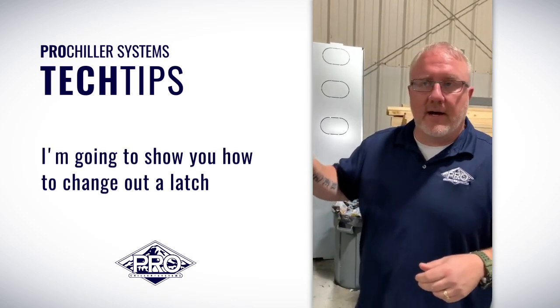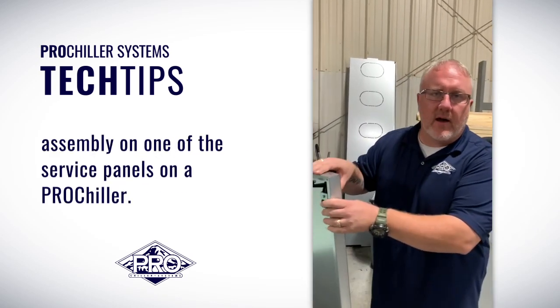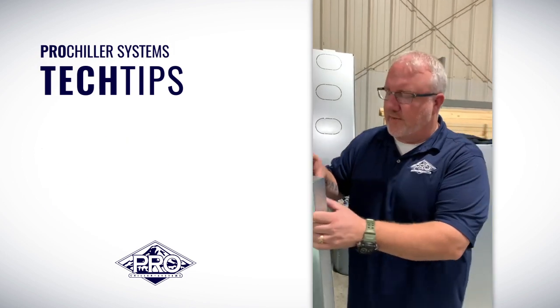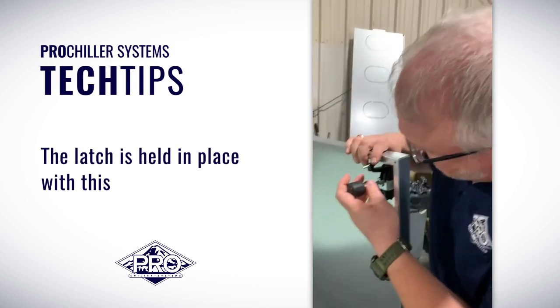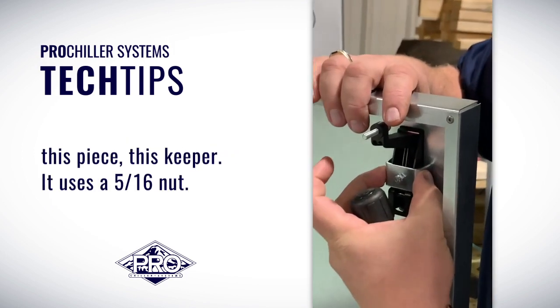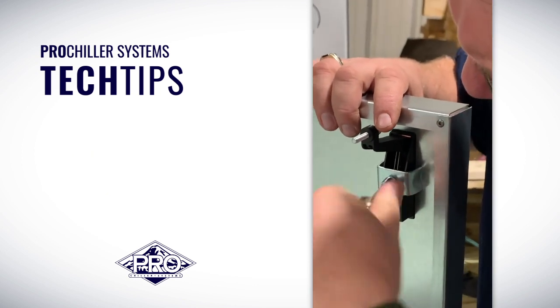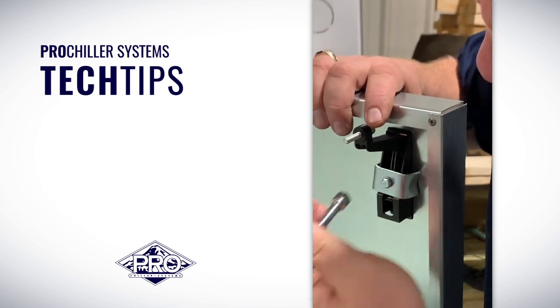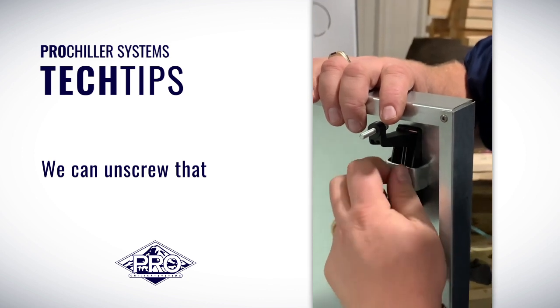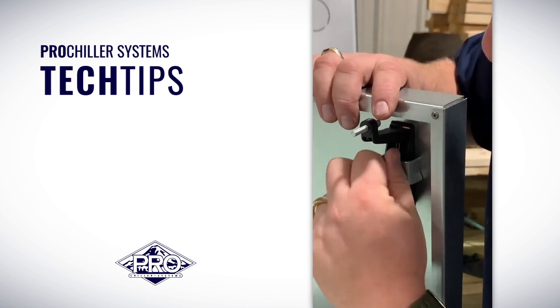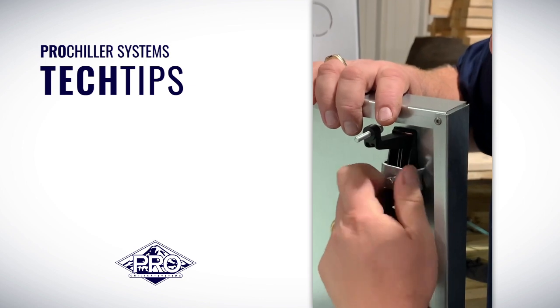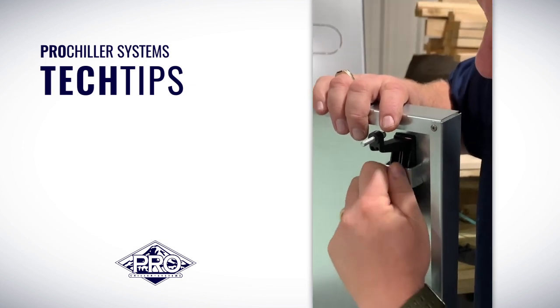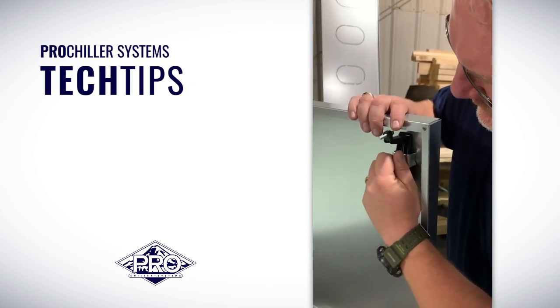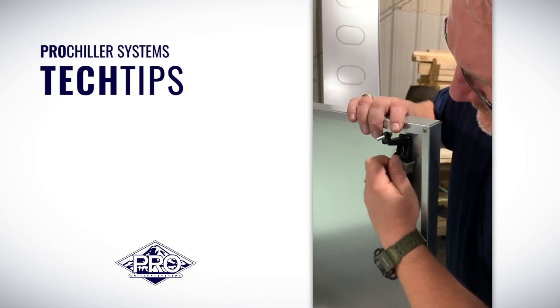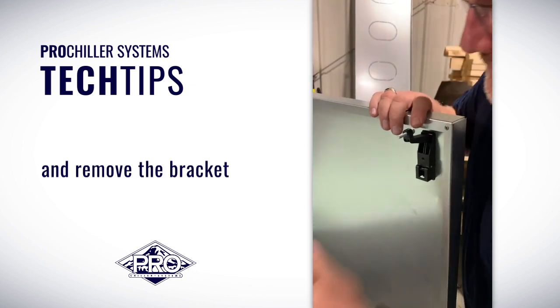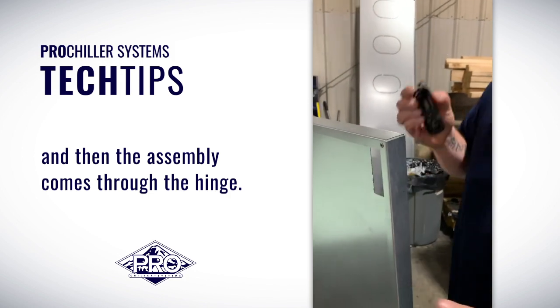I'm going to show you how to change out a latch assembly on one of the service panels on a ProChiller. The latch is held in place with this piece, this keeper. It uses a 5/16 nut. We can unscrew that and remove the bracket, and then the assembly comes through the hinge.